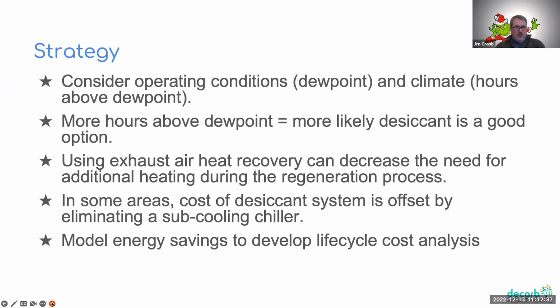And so your strategy here is to pay attention. Look at your operating conditions, your dew point, and the climate. See how many hours you've got. Use a desiccant where it makes sense, and use exhaust air heat recovery. That's kind of another talk I'd be happy to do sometime. And then pay attention to the costs of these systems. If you're using a desiccant instead of cooling, you might be saving some money that helps offset the cost of the desiccant system. And I'll stop there.